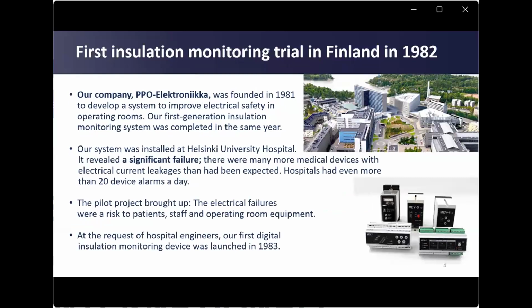This is how it all started. Our company, PPO-Elektroniikka, was founded in 1981 to develop a system to improve electrical safety in operating rooms. Our first generation insulation monitoring system was completed in the same year. Our system was installed at Helsinki University Hospital, and it revealed a significant failure. There were many more medical devices with electrical current leakages than had been expected.